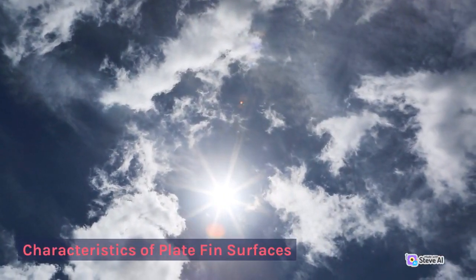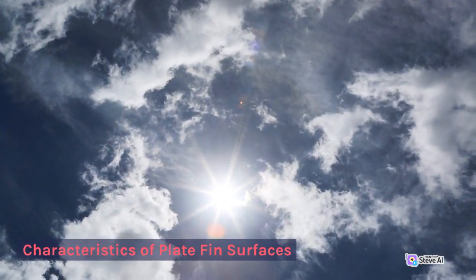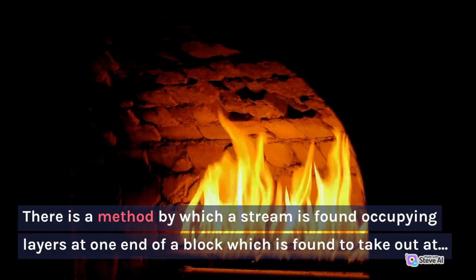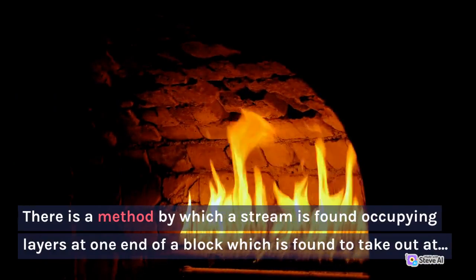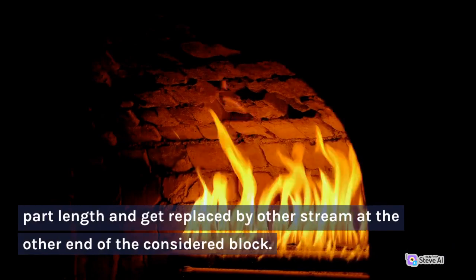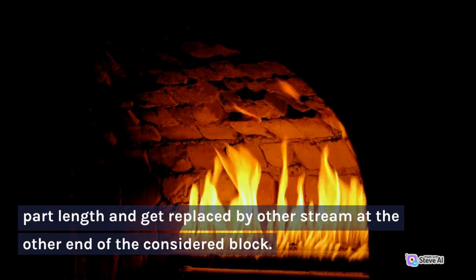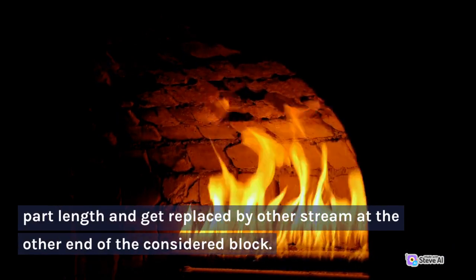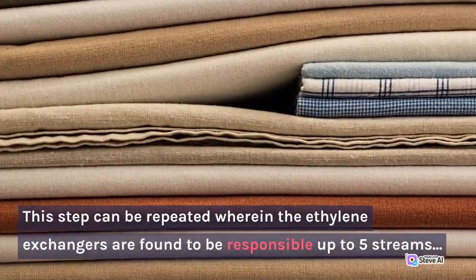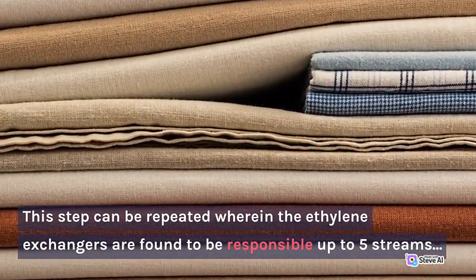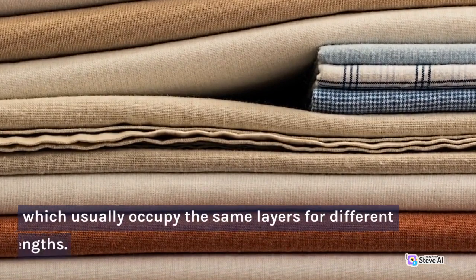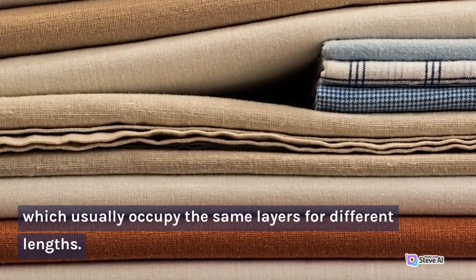Characteristics of plate fin surfaces. There is a method by which a stream occupying layers at one end of a block is taken out at part length and replaced by another stream at the other end of the block. This step can be repeated, so that exchangers can handle up to 5 streams, which occupy the same layers for different lengths.